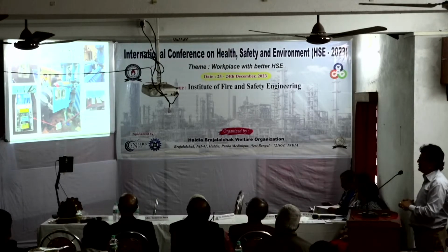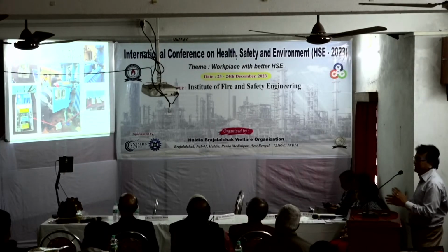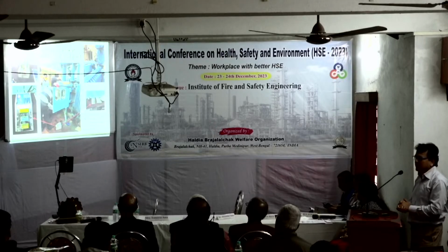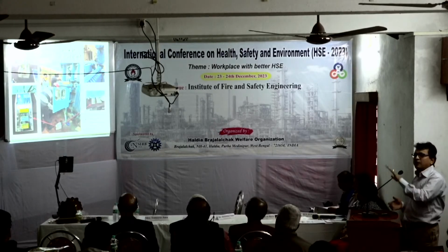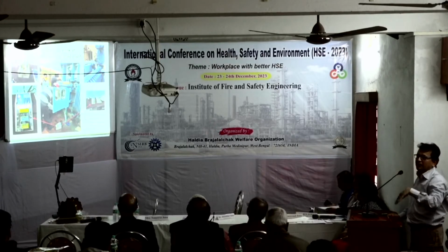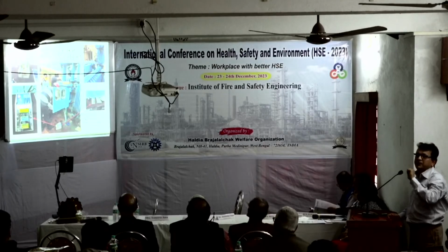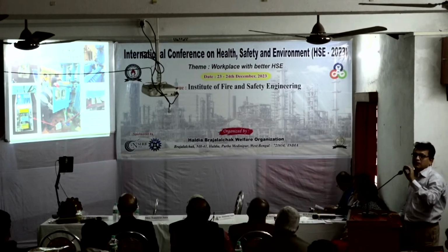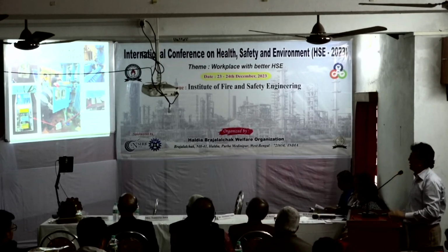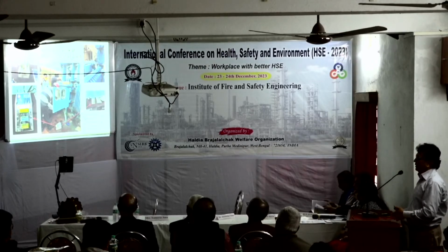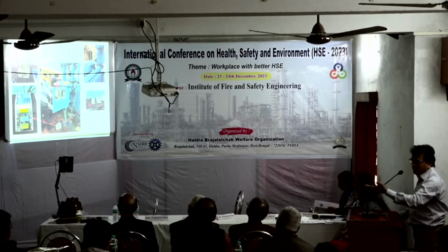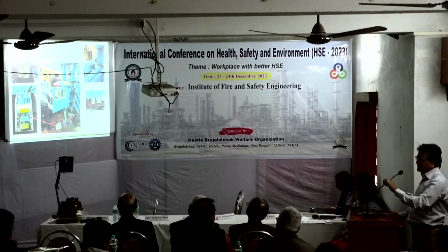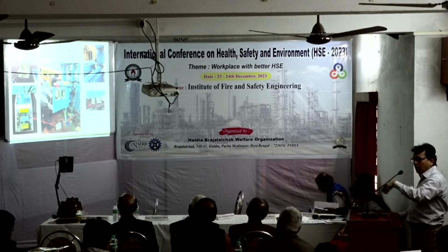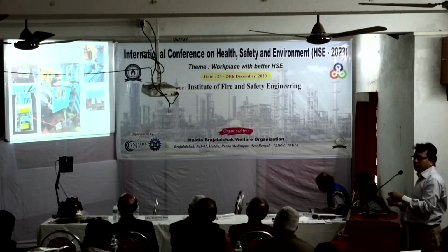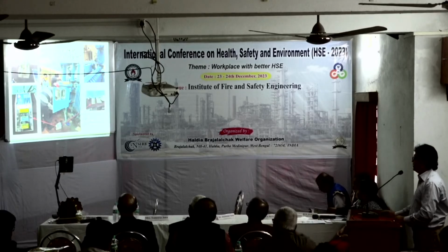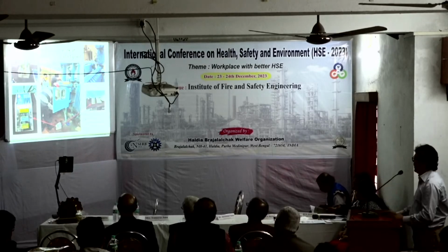The second part of this project is based on NTPC. NTPC required this type of moisture sensor for their different plants. There are more than 50 to 55 thermal plants all over India, one of which in West Bengal is Farakka. Their requirement was that since the transformer is far away from the control room, we measure the moisture of the transformer every time, 24/7. So we developed this type of sensor and mounted it in the transformer.